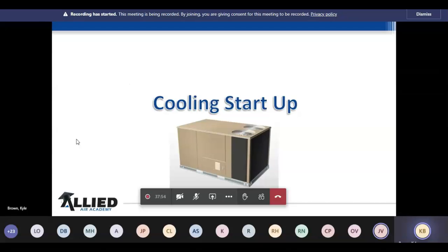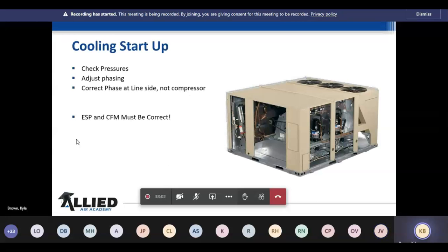Cooling startup. So we've gotten the unit on the roof. We're doing good. Everything's checked out so far. We're getting our power hooked up. Now we want to fire this unit off. And here's the configuration I talked about with the blower just now.